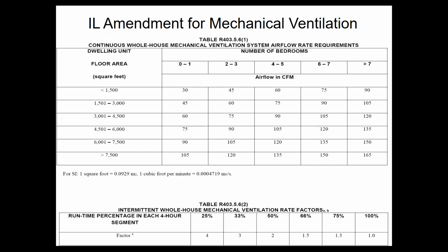The thing I want to point out about this is these numbers, 60 and 90 and everything else in this table, that's if the ventilation system is running 24/7, nonstop. If you want to cycle the fan, then you have to look at the table down below and apply these factors. So if you want to run the fan only 30 minutes out of each hour, you need to double the numbers. So 60 becomes 120, 90 becomes 180 in my 2 examples. If you want to run the fan 15 minutes out of the hour, you need to quadruple the numbers. So 60 becomes 240, 90 becomes 360, right? So you're probably better off running 24/7. Otherwise, you get too high of air coming into the inlet of the furnace heat exchanger.